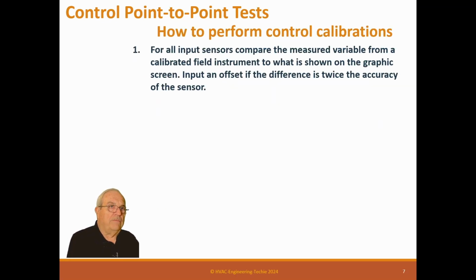For all input sensors, compare the measured variables from a calibrated field instrument to what is shown on the graphic screen. Input an offset if the difference is twice the accuracy of the sensor. So if you have a sensor that's plus or minus 1 degree, and your sensor is 2 degrees off, you may or may not put an offset in the system. And the reason is because if the sensor can be plus or minus 1, it can be within the 2 degree range. So maybe there's no reason to do that because you have 2 degrees on the screen.